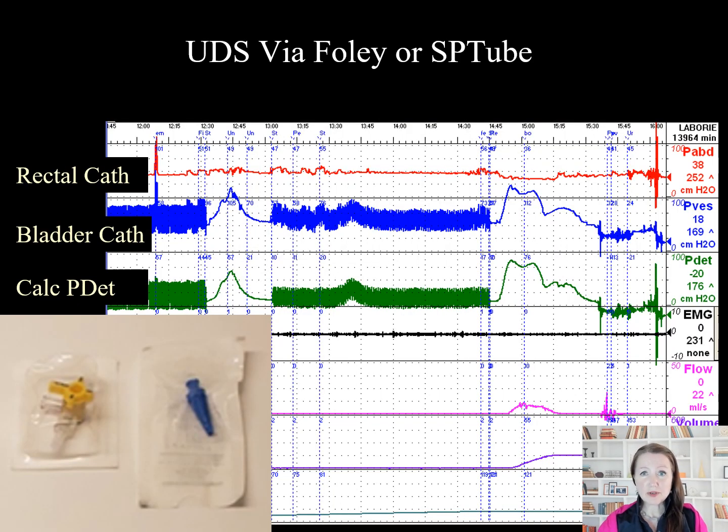If the test needs to be performed through an indwelling catheter, you will need a three-way stopcock and a Christmas tree adapter. Both the fill line and the urodynamics measurement tubing for the Pves will be connected to the three-way stopcock, then attached to the drainage port of the Foley.